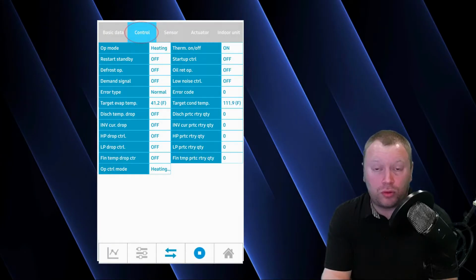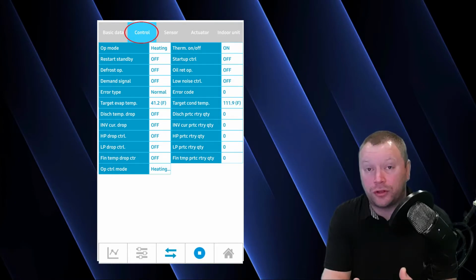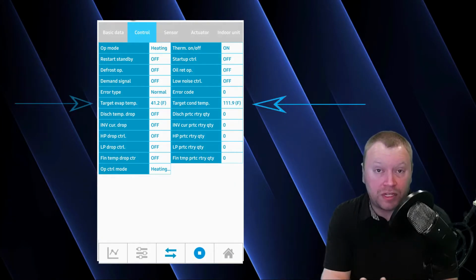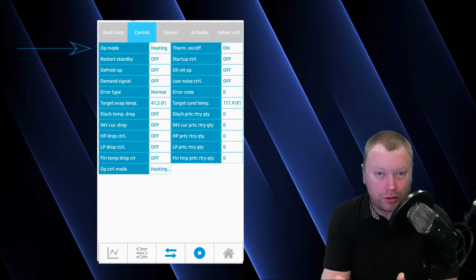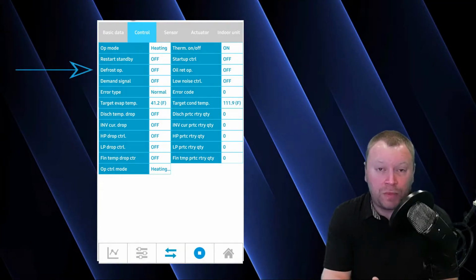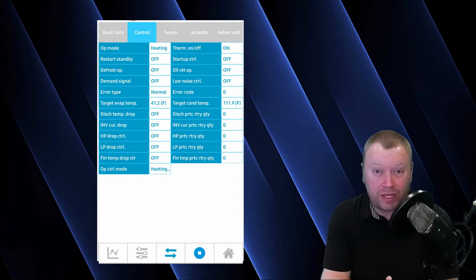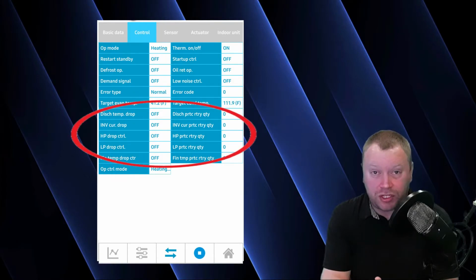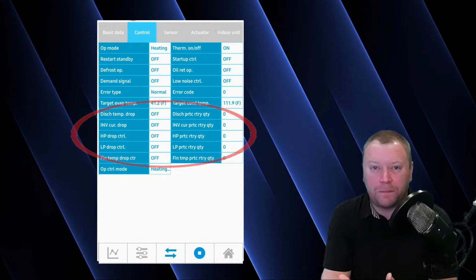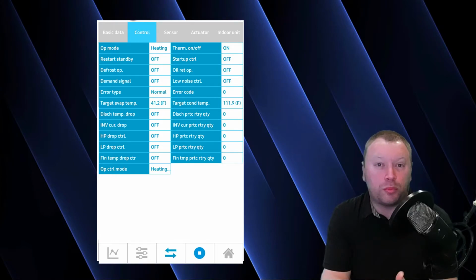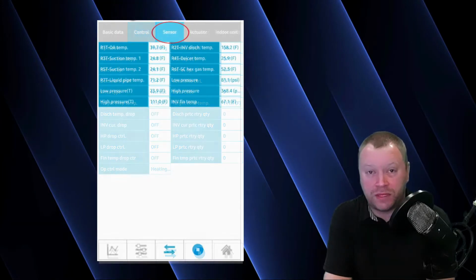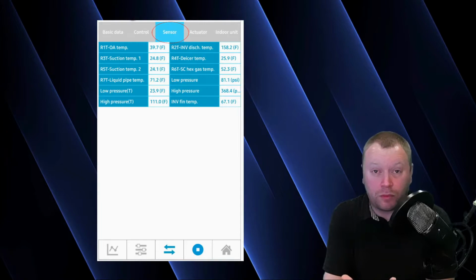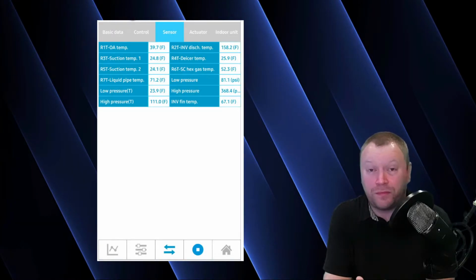So when you look at the control tab, it's going to be your system control, your target values, your target condensing temperature, your target evaporating temperature. It's also going to show you what mode you're in, heating or cooling, and then whether or not your system is currently going through defrost. In addition, the control tab also has all of your safeties. We call those protections. So if your unit is currently limiting its operation due to high pressure protection or low pressure protection, it would indicate this in the control tab. Now in the sensor tab, this tab's going to have all of our pressure transducer and thermistor data from the outdoor unit.